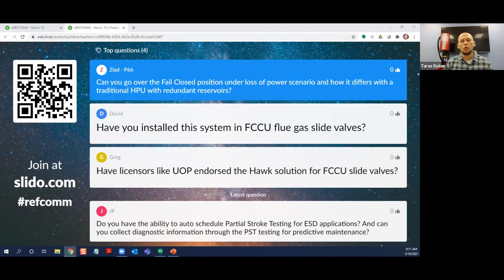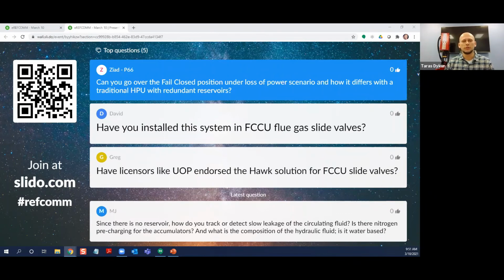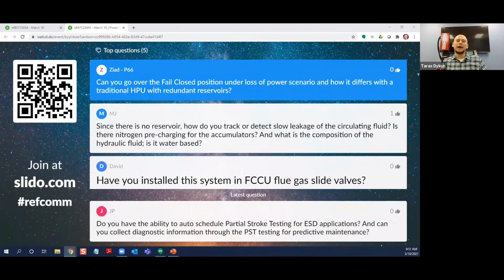So the next question: can you go over the fail close position on the loss of power scenario and how it differs with a traditional HPU with the redundant reservoirs? I'm not actually familiar with redundant reservoirs. Oh, you're probably talking about accumulators. So actually, current units and actual specifications on UOP and Axens specs call out that on the loss of power to the actual controller, the unit has to lock in place.